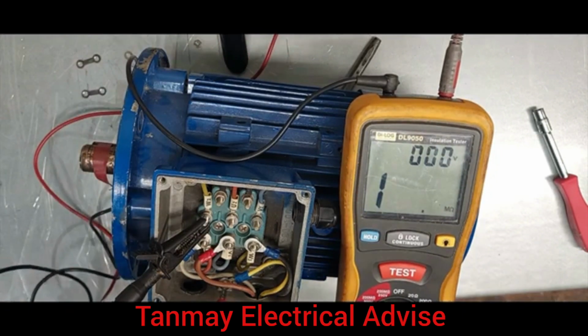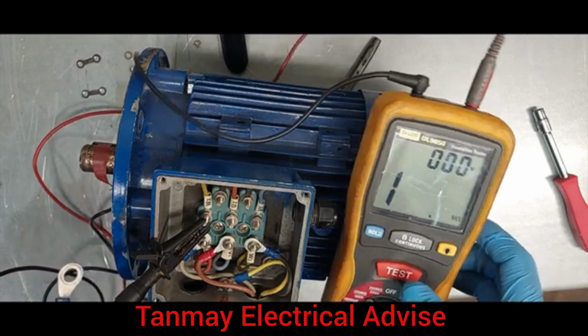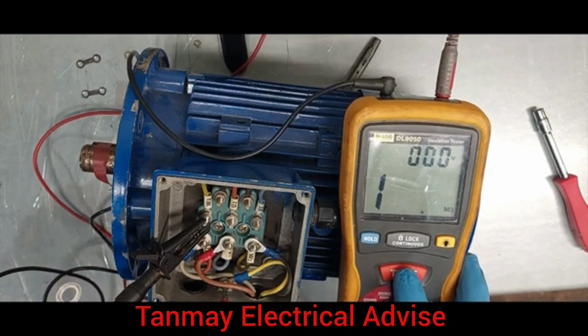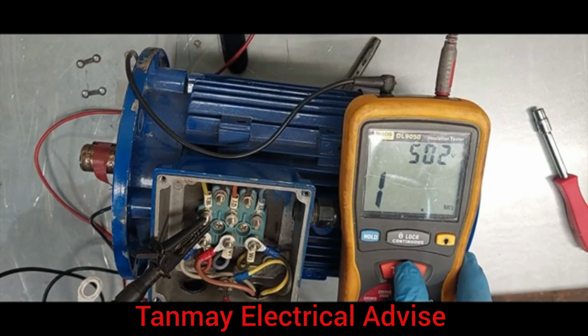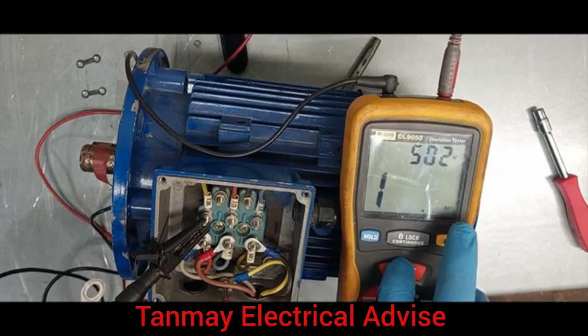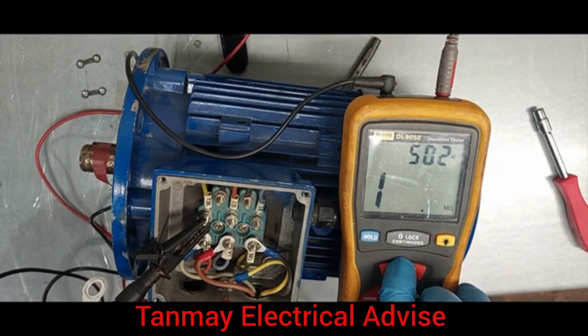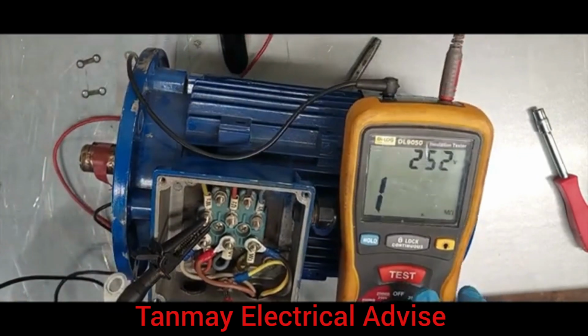So now we put it on the chassis, the earth, and we inject 500 volts as we've set it here. If we hold where it says test, push it, now 500 volts has gone inside, and we can see that we're having 1 mega ohm here. So this is good. The W2 has passed the insulation test.